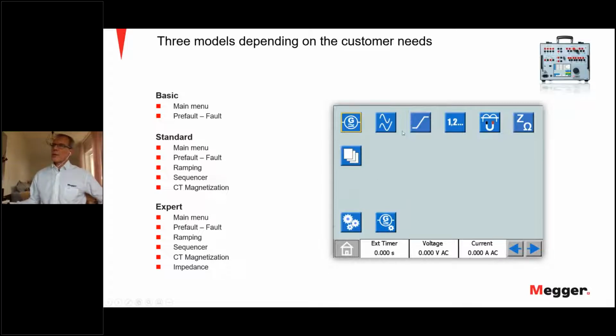In the basic model, we have two instruments. What you see here is the touch screen on the SVERKER 900, and the symbol for the main menu is here, and the pre-fault fault instrument is here. So these are the two instruments you have in the basic model. In the standard model, you add the ramp instrument, the sequencer, and also the CT magnetization instrument, which is used to test the current transformer magnetization curve and find the voltage knee point. The expert model has all the instruments, and that also includes the impedance instrument, which is used when testing, for example, distance protections.